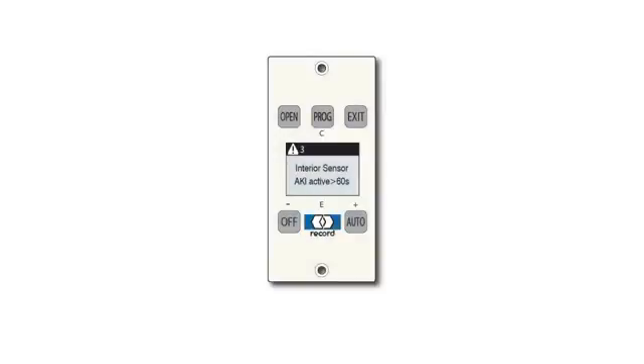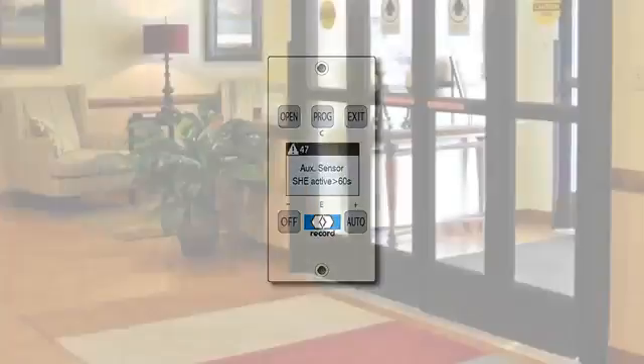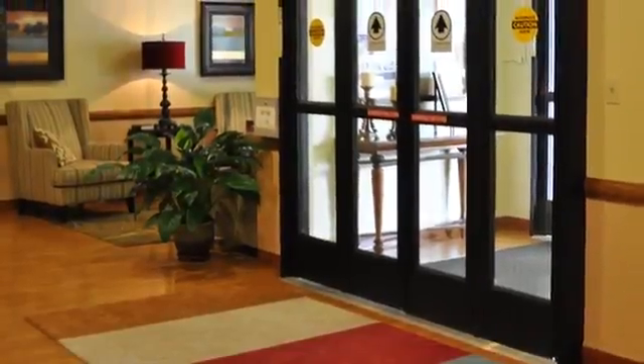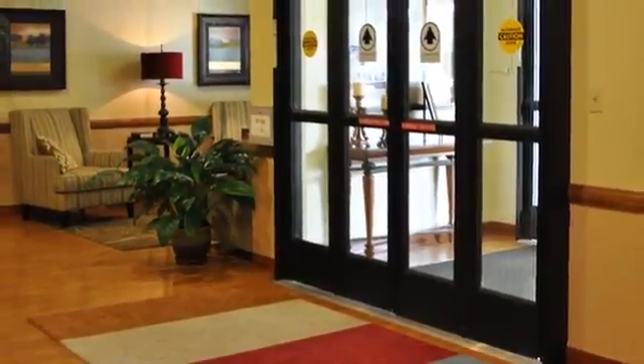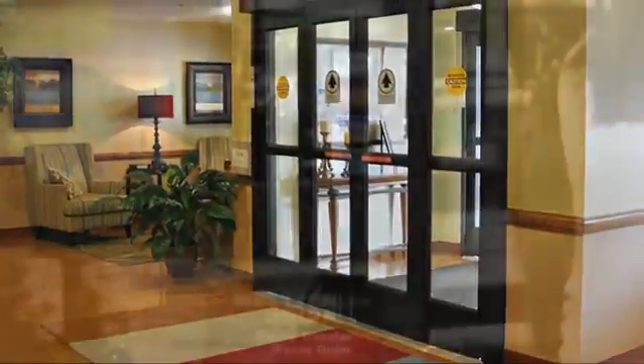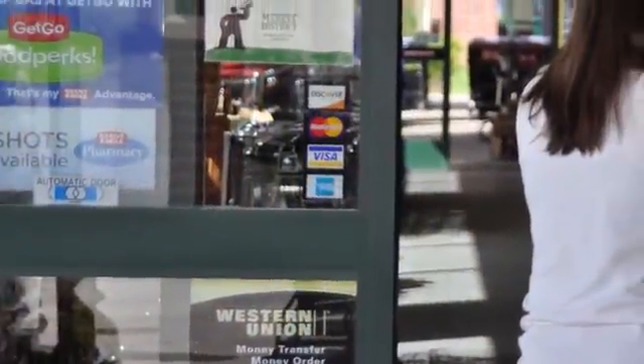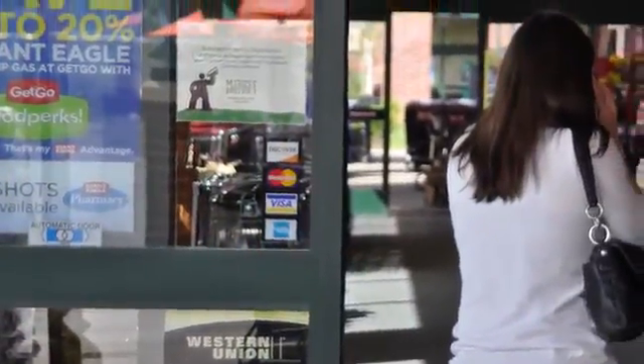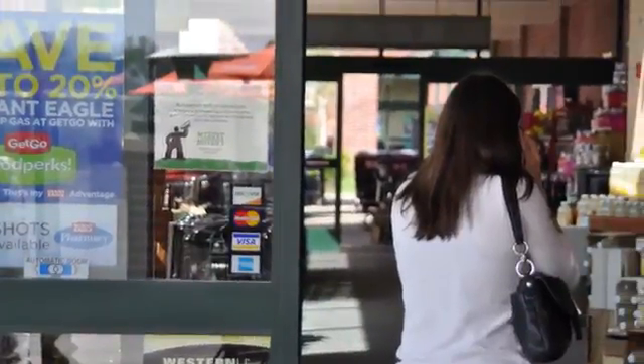The Smart Panel will also display an error if a sensor detection area has not cleared within a reasonable amount of time. The most common causes are changing of rugs, mats, or signage, or adding or removing furnishings. When this happens, allow up to 5 minutes for the sensor to relearn the environment and the door should return to normal operation. Any moving objects, such as signs blowing in the wind, should be secured or moved away from the door.